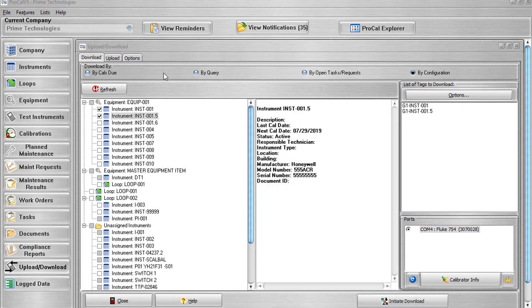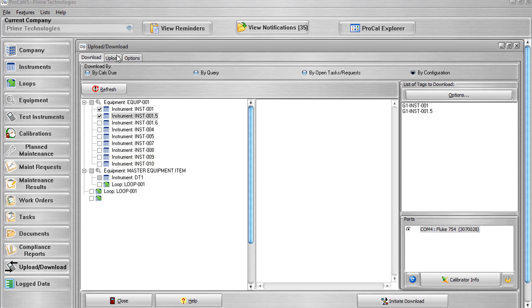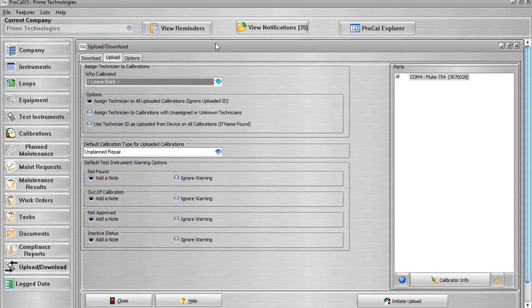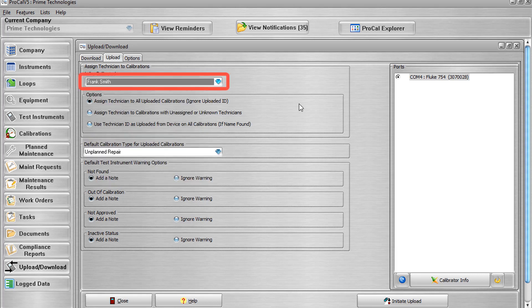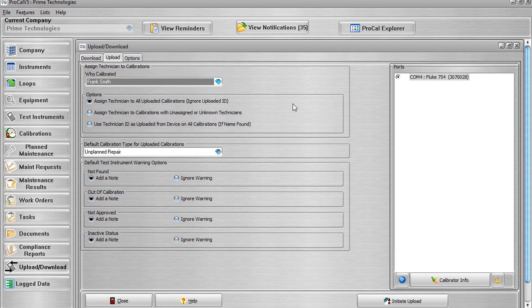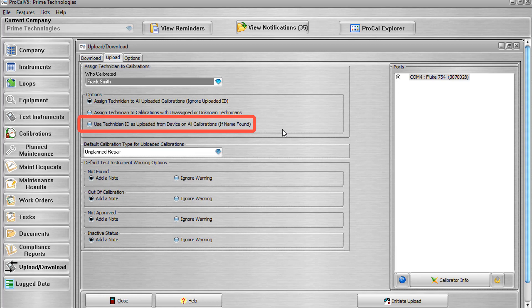Once your work is complete, you'll want to upload those calibrations back into ProCal V5. Just connect your calibrator again, navigate back to the Upload Download screen, and this time open its Upload tab. This tab will give you various options that you can apply to your upload. In the Assign Technicians to Calibrations section, the Who Calibrated field is used to assign the selected technician to all calibrations or calibrations with unassigned or unknown technicians which are uploaded from the calibrator, regardless of which ID is sent back from the connected device. The name will appear in the Who Calibrated field of the calibration record. Selecting the Use Technician ID as Uploaded from Device on All Calibrations radio button will apply the technician ID associated with the calibrator to the calibrations that are uploaded, as long as the technician's name has been entered into ProCal V5.